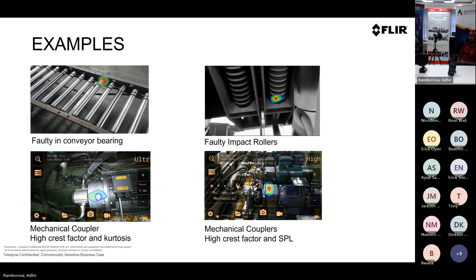I think somebody asked that potential question: can you inspect a bearing that's not in the line of sight? In actuality, it's a bit difficult to do that because sound obviously travels and bounces. So you want to make sure you can see it, just for ease of use. There are some limitations with multiple technologies when it comes to closed bearings, unfortunately, and the SI2 is no stranger to that. However, if used properly, it's definitely going to help you solve and pick up these faults and problems a lot faster than any other technology.